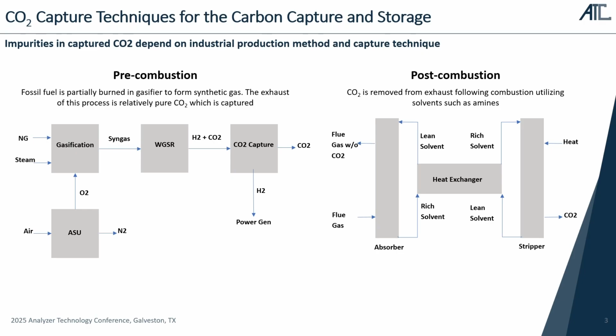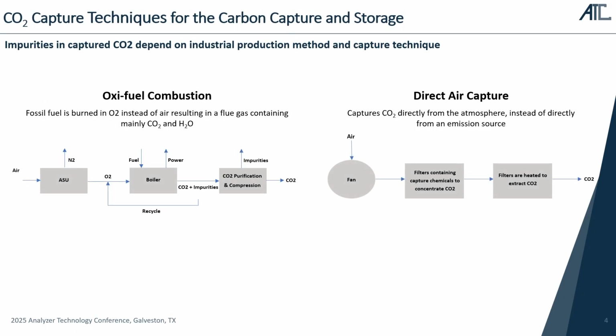The hydrogen can be used for power generation, and the CO2 can be used for either utilization or storage. Post-combustion capture is probably the most common that we see, mostly because it can be retrofitted directly into industrial processes. In post-combustion capture, we take the flue gas and route it through a solvent-rich bed, usually amines at this time, that have a special affinity towards carbon dioxide. The amine and carbon dioxide mix will then be heated to separate the carbon dioxide, and then it can typically be transported. Next is oxy-fuel combustion. This is basically removing the air out of the equation with combustion. As everyone probably knows, when we combust with air, we have a lot of opportunity to create oxides of nitrogen. Combusting with pure oxygen results in an almost complete combustion reaction. So our main byproducts are just carbon dioxide and water. The moisture can be easily dropped out, and then we have captured CO2.